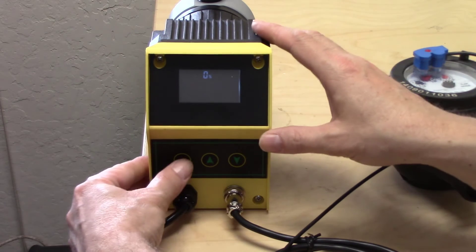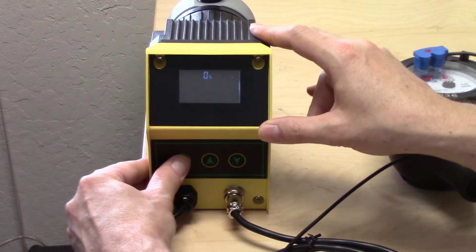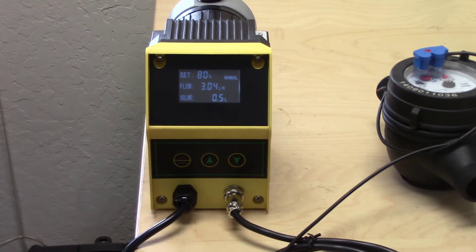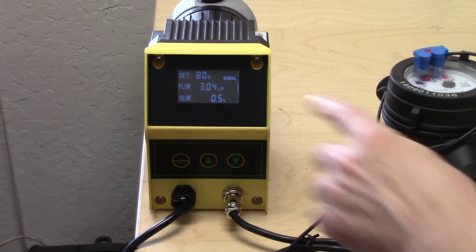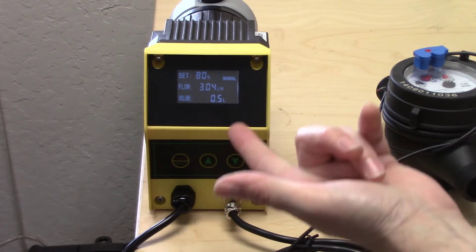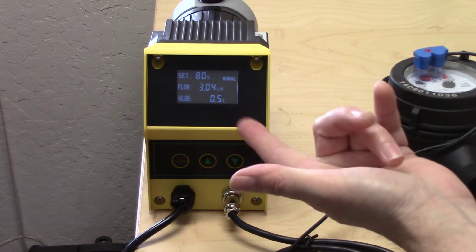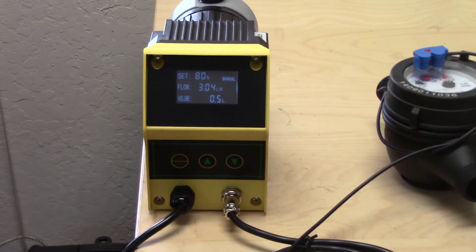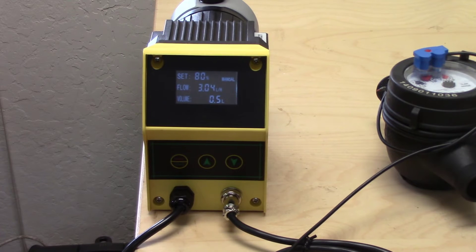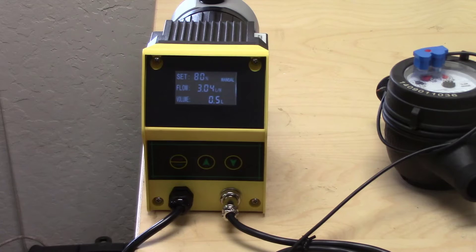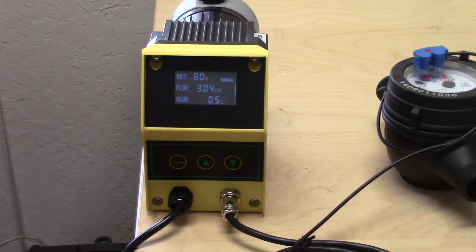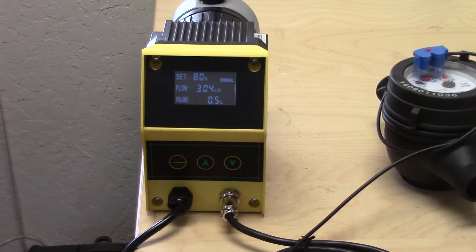When you press and release the start stop button, it will go into whatever mode it was programmed in last. Right now it's in manual, which is why you can hear it pump. You'll leave it in manual mode or change it to manual mode in order to prime the pump, and then after the pump is primed, you'll go back and set it to the pulse setting.